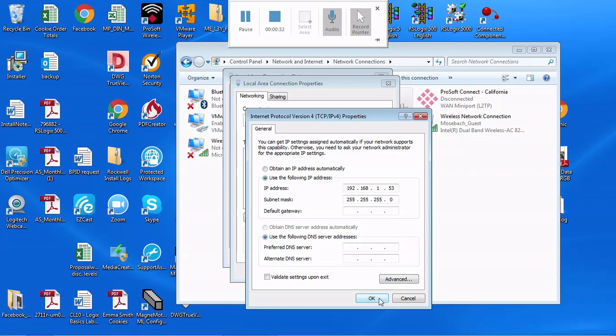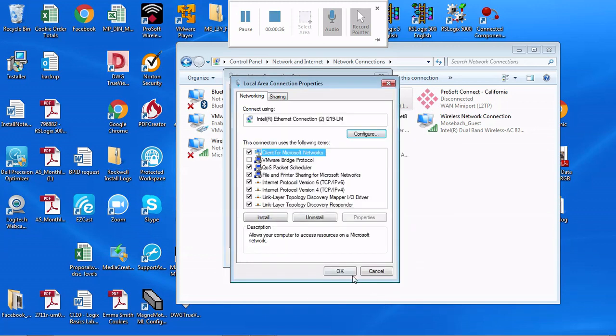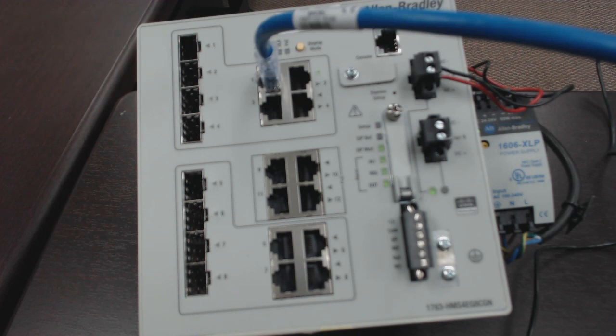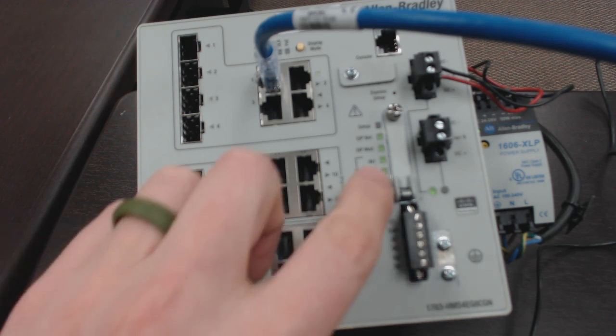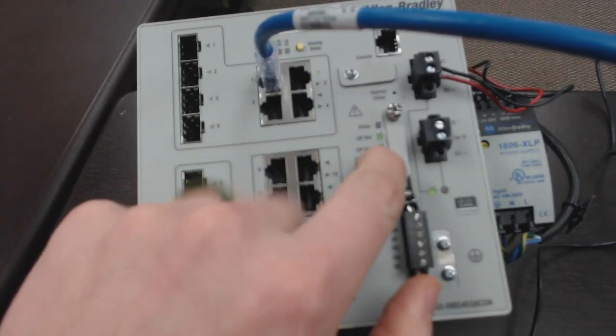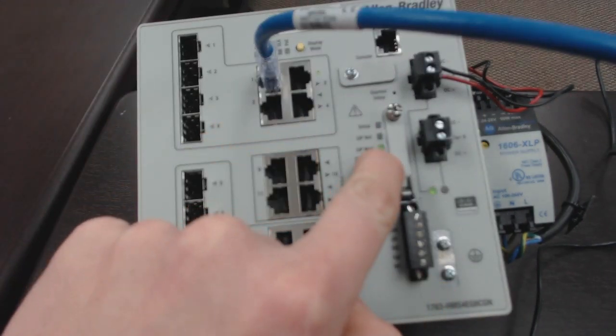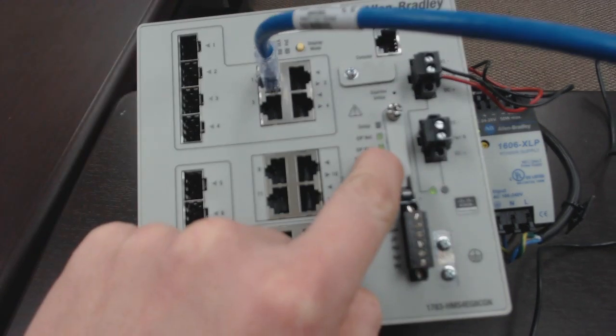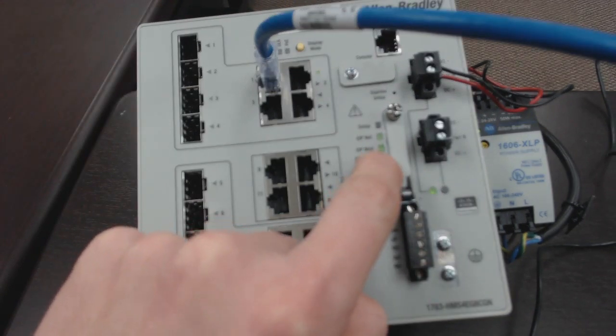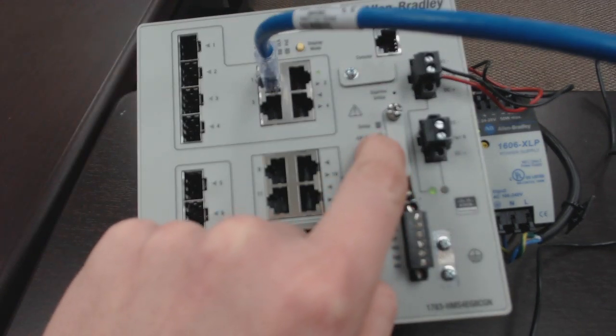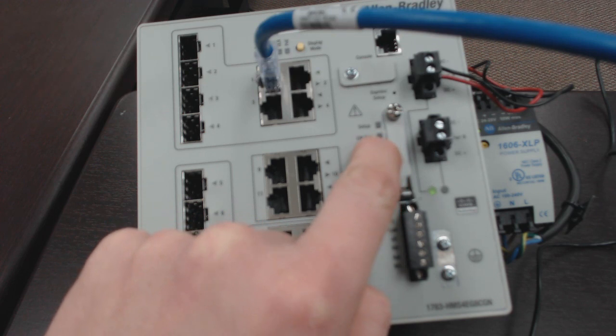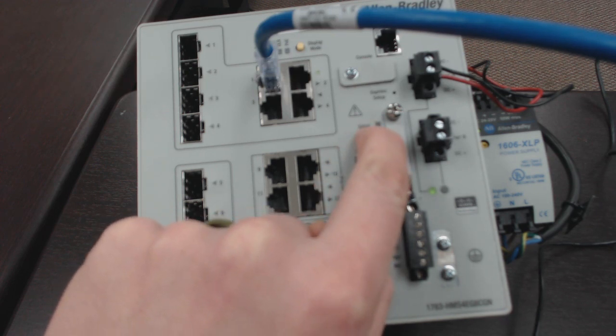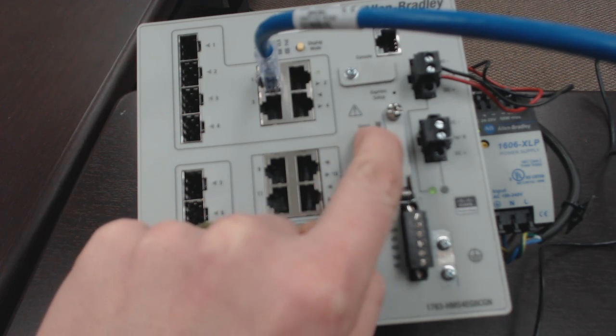I want to show you what to wait for when the switch reboots before going ahead and trying this. What you're going to notice is that the Ethernet IP module light is now solid. That means the switch has been configured, it has an IP address, it's happy. The net is still off because there's not really anything talking to it. And our setup light is off, so we're not in setup mode anymore.